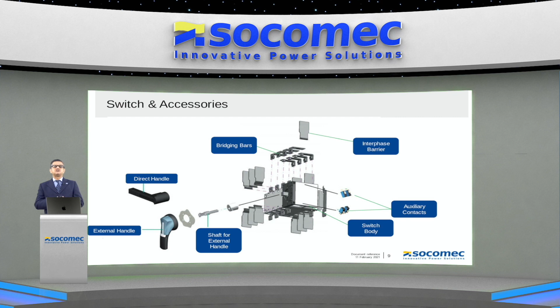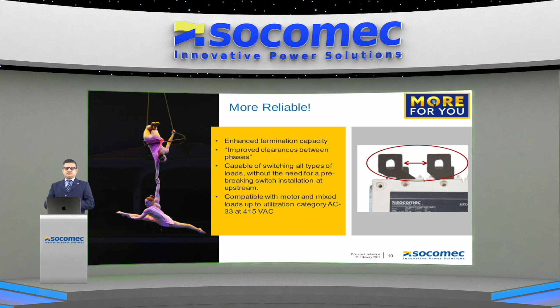Now let me go point by point about why we call it more reliable. It's because of enhanced termination capacity, improved clearances between the phases, and it's capable of switching all types of loads without the need for a pre-breaking switch installation upstream. This makes it compact, integrated, and compatible with motor as well as mixed loads, going all the way up to severe utilization category AC-33 at 415 volts AC.